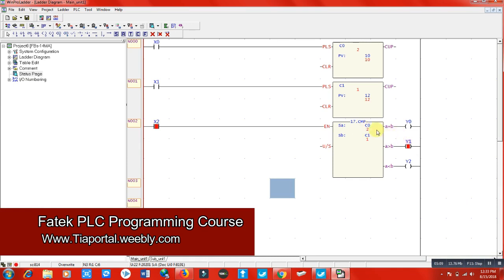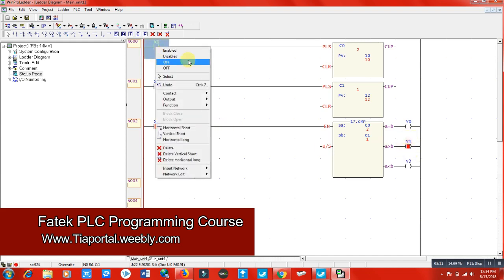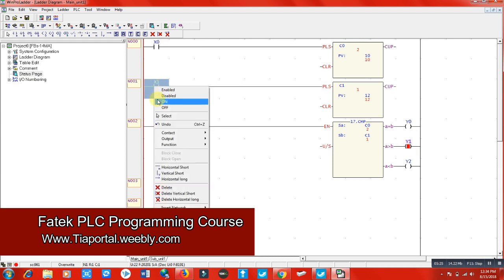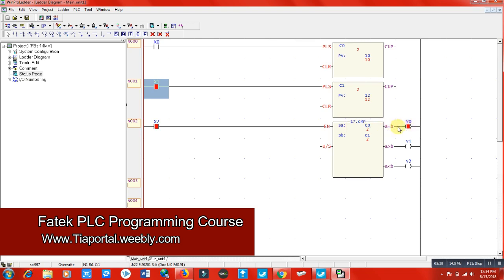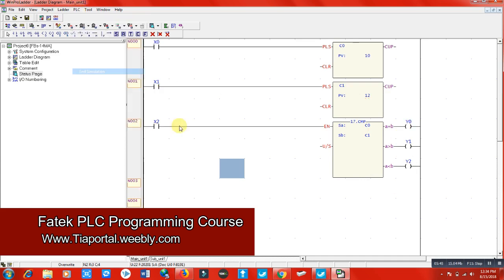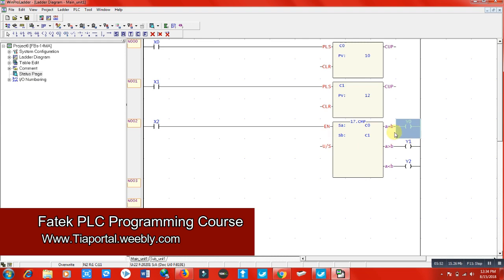What if we want to switch on more outputs? For example, I would like to switch on y0 through y4 when A equals B — when both counters become the same. To do that, I'll use a memory coil m0 here as the output, and then use the normally open contact of m0 to energize several outputs when m0 is switched on.